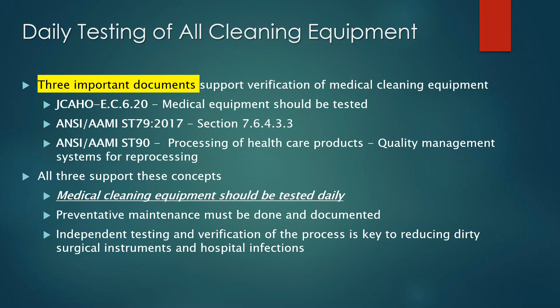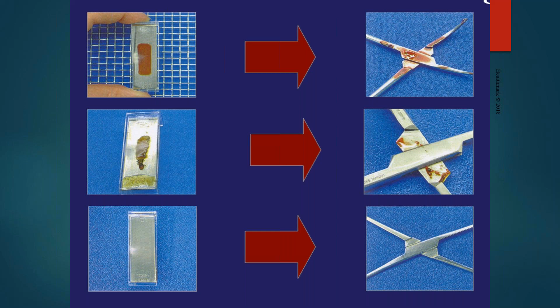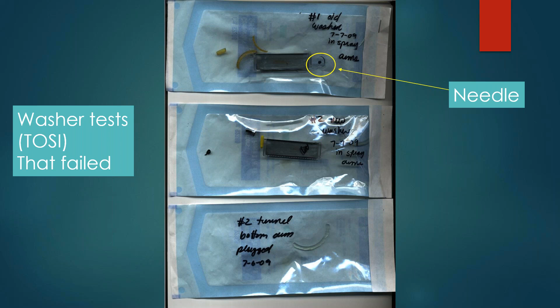This is just a little thought about what a surrogate device would be. Instruments, especially hinged instruments with box locks, become soiled with blood. The blood, as much as we talk about maintaining moisture, sometimes does begin to dry and harden, and getting into those specific areas becomes difficult. And if you have a test that simulates that same sort of action, then you're much more assured of your outcomes. Just some other things found in a washer and other reasons that your washer can fail. Needle found in a washer, that's not very good sharps safety. But as you can see, broken O-rings, tip protectors, all of those things are going to impact the impingement action and the function of your washer. And of course, tests fail when these things are present.